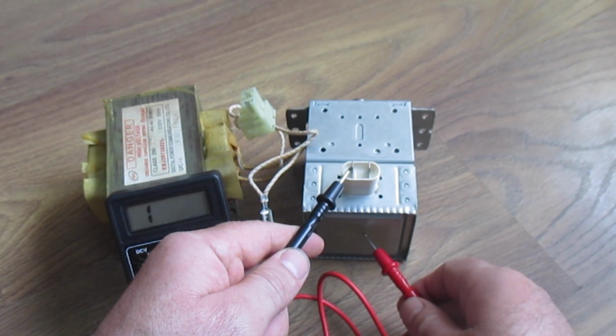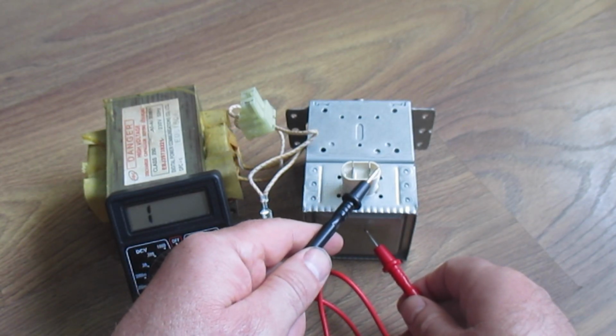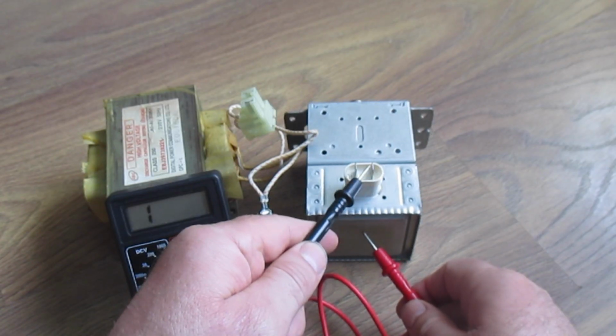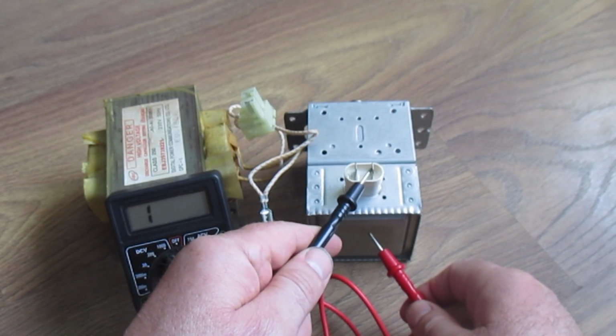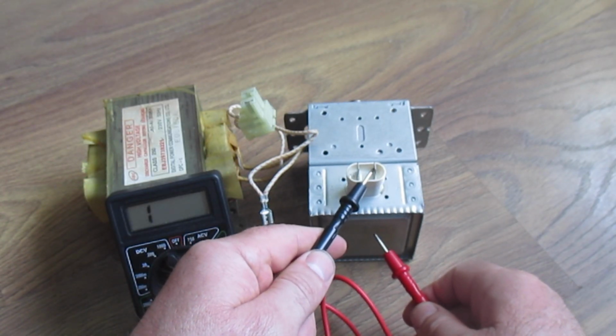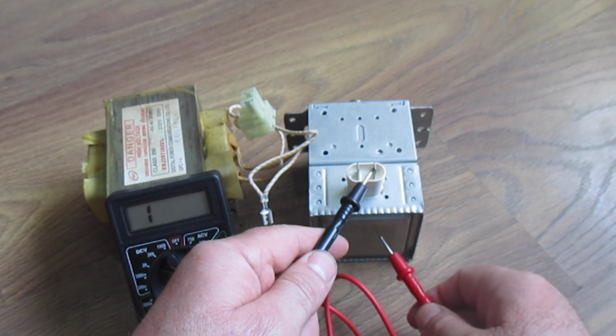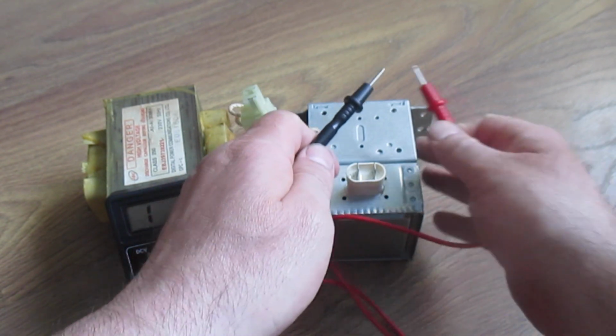Next, I check for breakdown on the case. I place one probe on the plug contact, the second probe on the case, and it shows one, no breakdown. I also check the contact of the second plug in this way. Everything is fine here too.